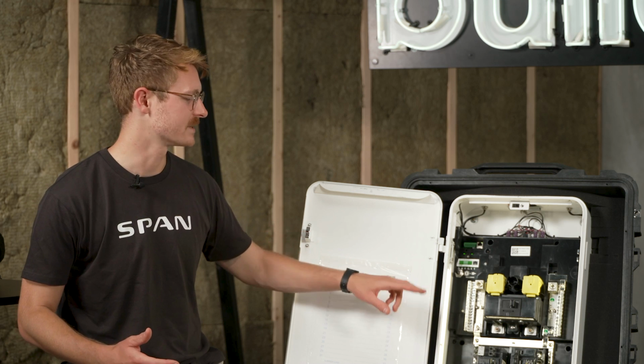So in other words, you could use this as your main panel and put all your main loads on it, but put all your lighting circuits in a sub panel. You'd just have less visibility into what's happening, but it could still run all the functionality. And every variation in between, right? You could double up lighting circuits on a tandem.